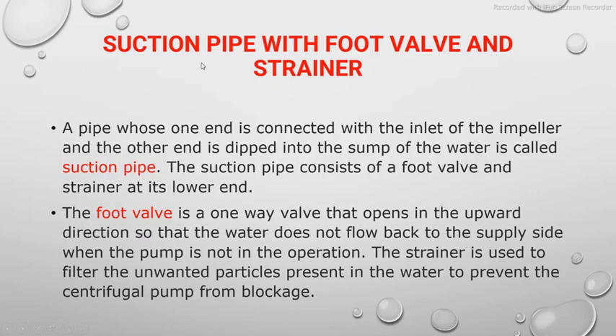The suction pipe is a pipe whose one end is connected to the inlet of the impeller and the other end is dipped into the sump of water. The pump is connected to a sump so that it can extract water from it — this pipe is known as the suction pipe. The suction pipe consists of a foot valve and a strainer at its lower end. The foot valve is a one-way valve that opens in the upward direction so that water does not flow back to the supply side when the pump is not in operation.